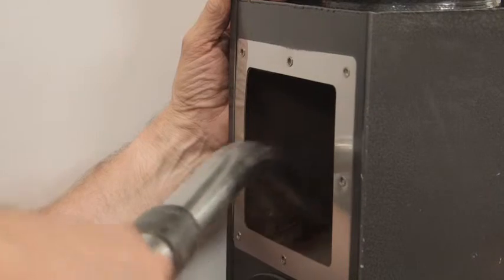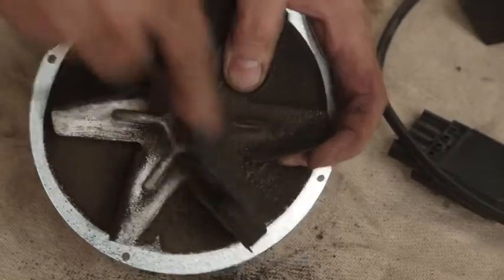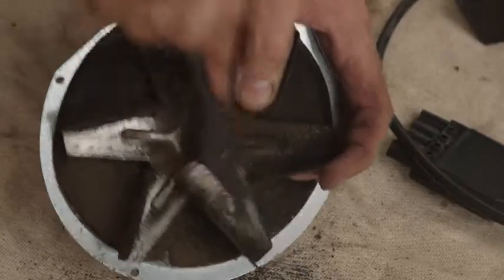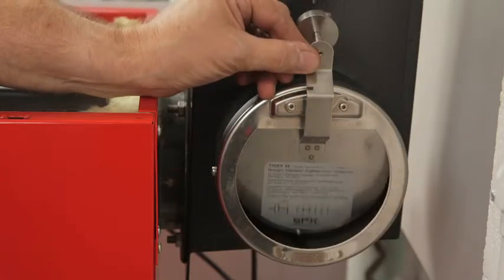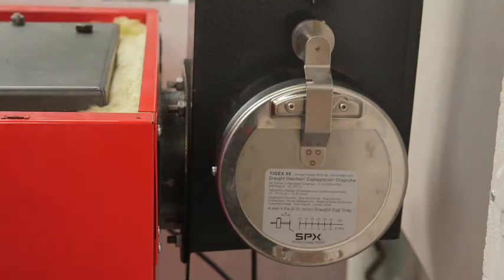Once you've been through all the standard checks, open up the access door to inspect the flue and fan box and clean out any ash you find there. You'll also need to clean the fan. Remove it and brush off any ash from the fan impeller. Make sure the draft stabilizers damper is free to move.